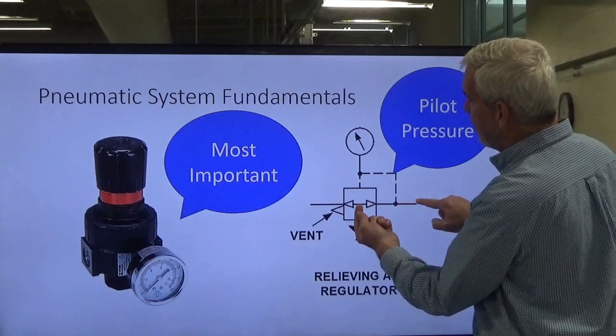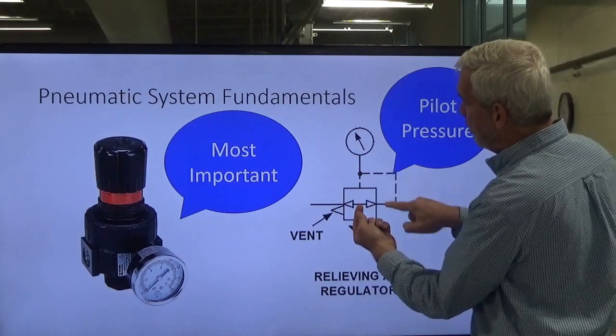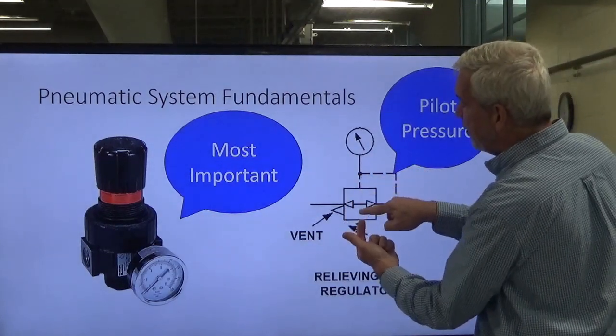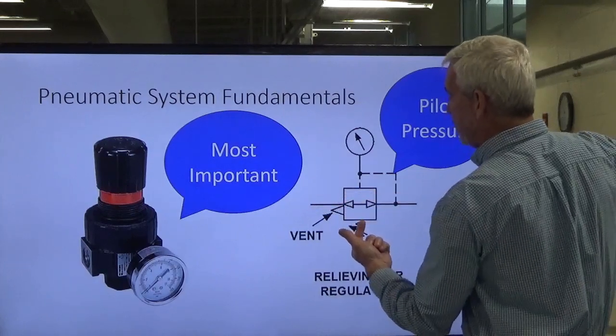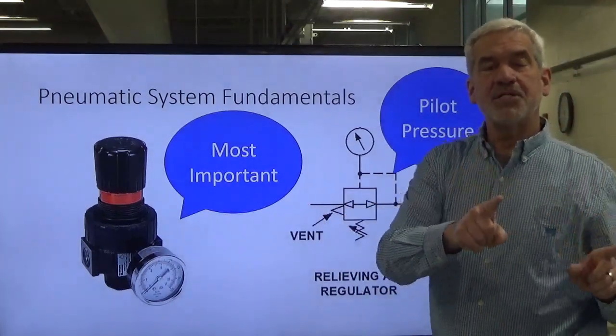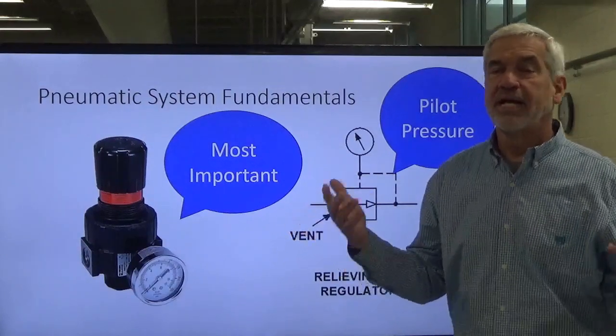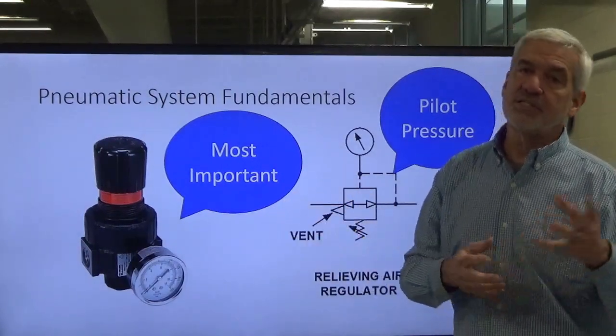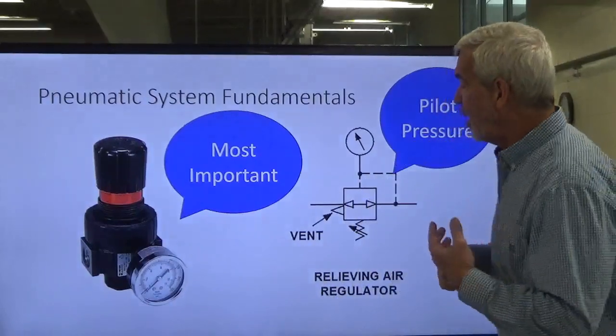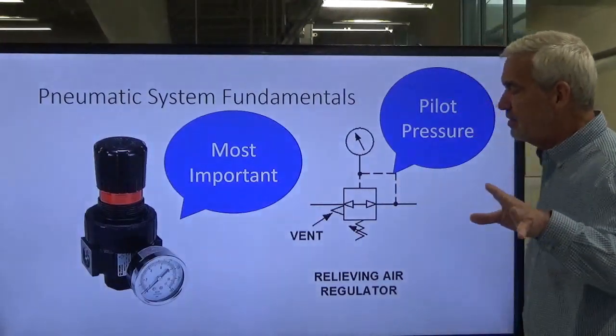If the system were to experience greater than 50 pounds, this pilot pressure is going to force the spool inside the regulator down and shut the air supply off, allowing it to dump to vent. That keeps our system intact and prevents too much pressure on the downstream side. That's another advantage of pneumatics over hydraulics - anything we exhaust goes out into the atmosphere.